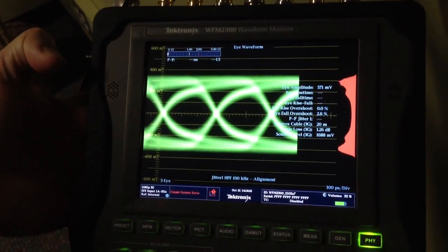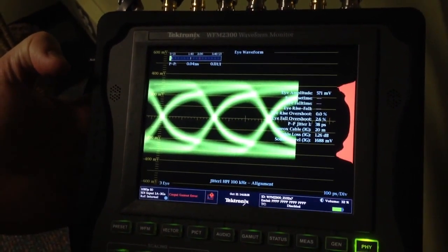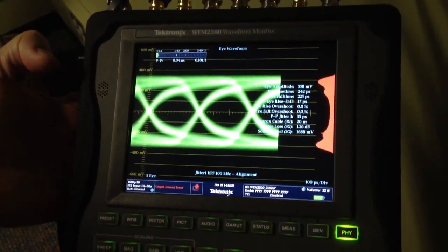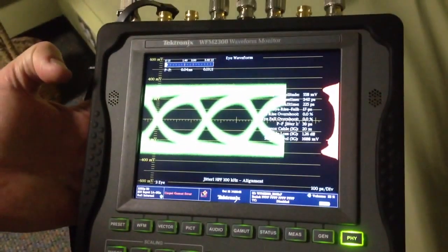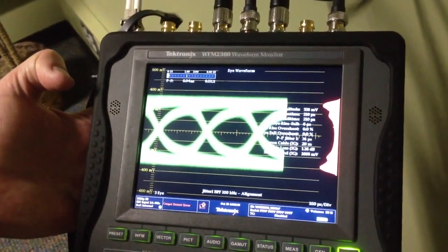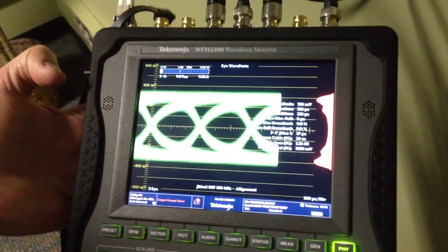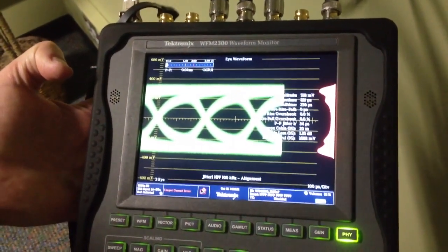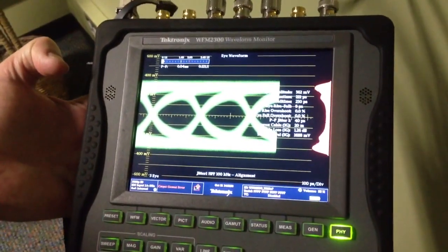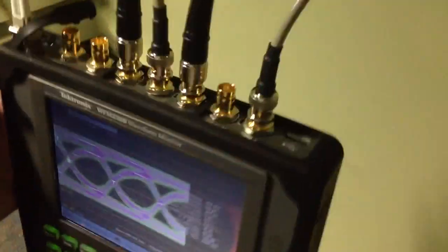So you can see that the amplitude of the signal has decreased and the bandwidth frequency response of the signal has also decreased because the rise time and fall time of the signal have gotten longer. So this stressing loop can be added either from a signal under test or going to a signal under test for length testing of the installation of a cable within a plant or testing the signal in a plant. So this adds an additional stressing system to here.